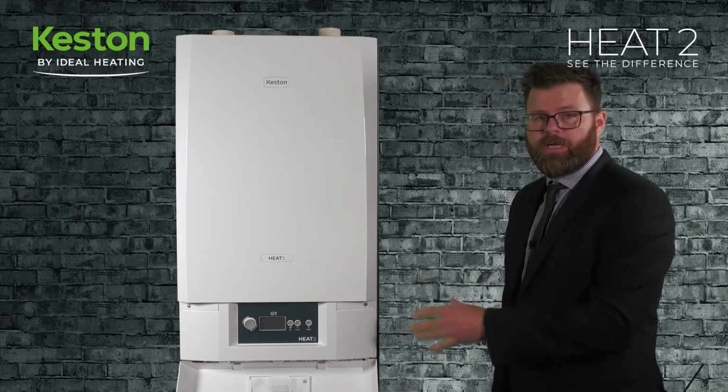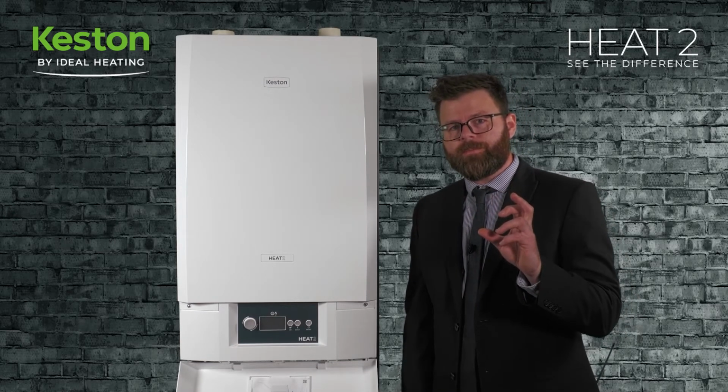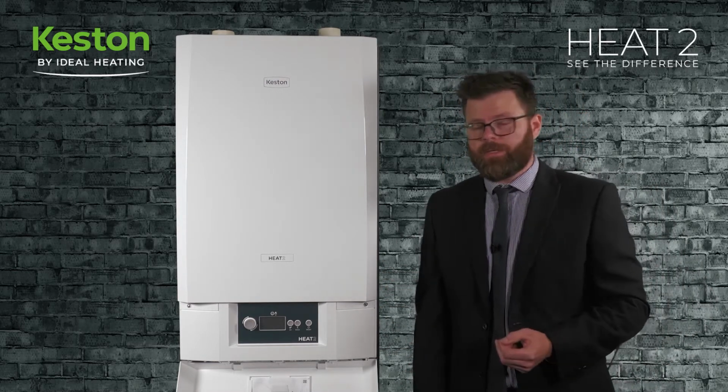If we want to cascade the boiler, we've got an accessory called the VariCan as well. I'll show you where that goes inside the boiler shortly. That's a small PCB which fastens in the control panel and allows you to daisy chain several boilers together, so up to 4 boilers on our header kits.